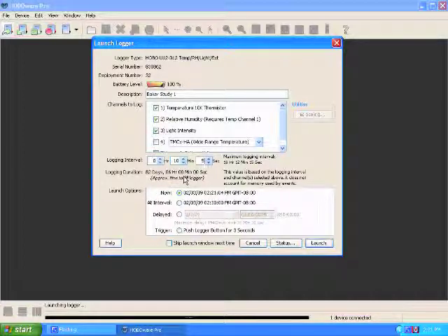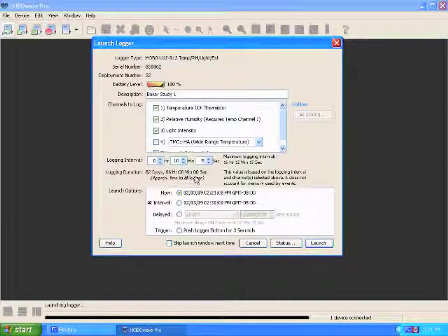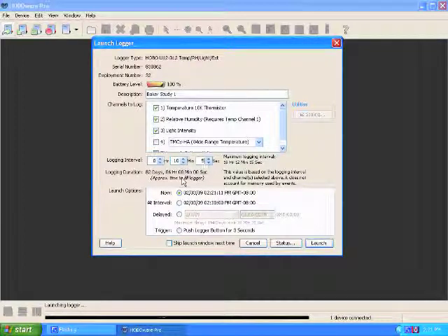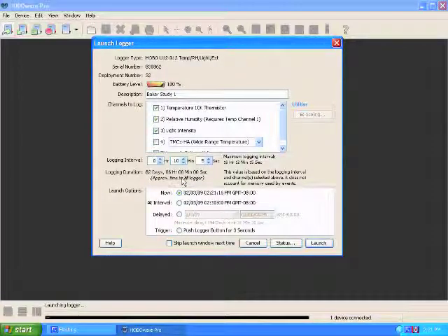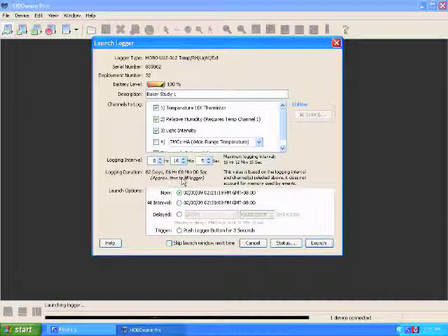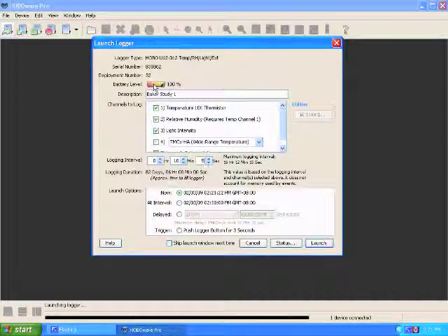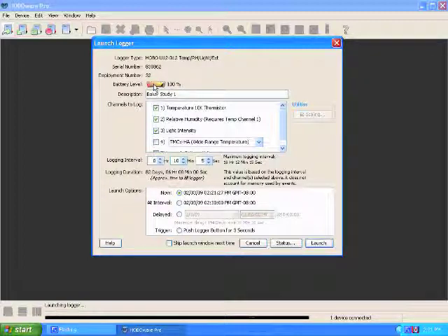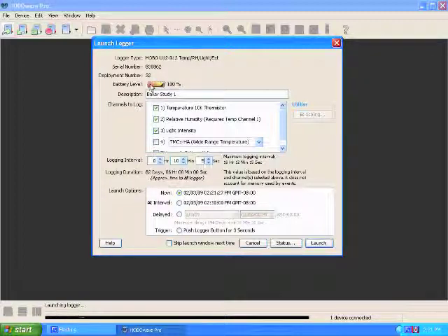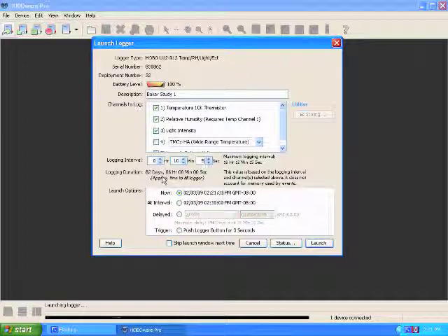One thing to keep in mind when you're doing this is the battery level. Your battery level will probably last as long as you're taking your study, even if it's getting on the lower side of the meter. So you're probably safe if you're just working for a couple of days. If it's very low in the red, you may start getting skewed readings and it might even shut off during your study. So you want to return it to Baker and trade you for a different one.